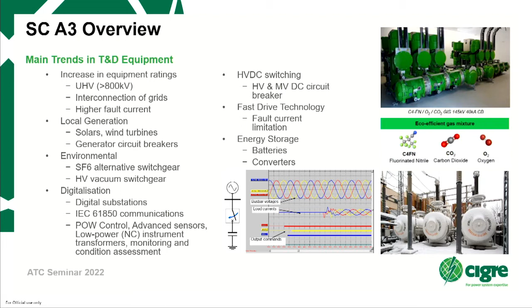Along with decarbonization, one of the most interesting topics in Paris was related to SF6-free switchgear products and projects. Now we have vacuum technology moving into higher voltages per single break. We have circuit breakers developed up to 170 kV. Air or CO2 is used as a main or carrier gas for insulation or for interruption.